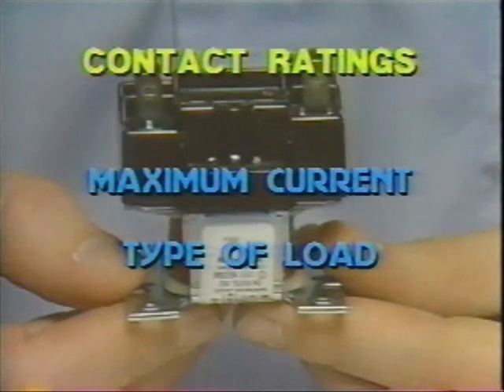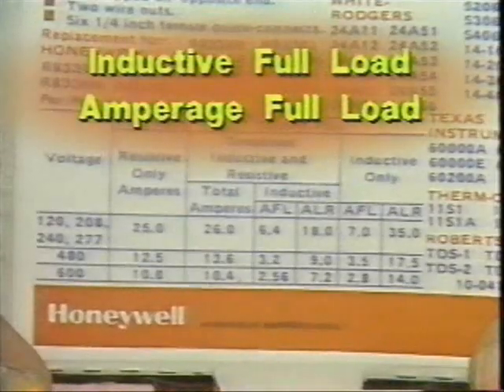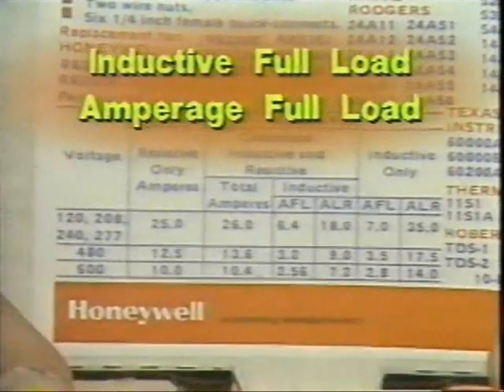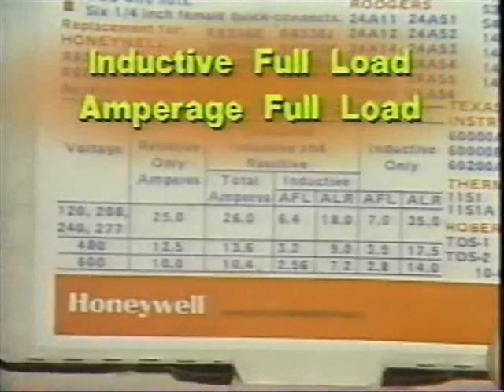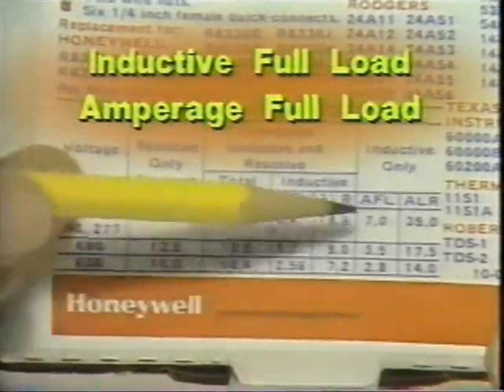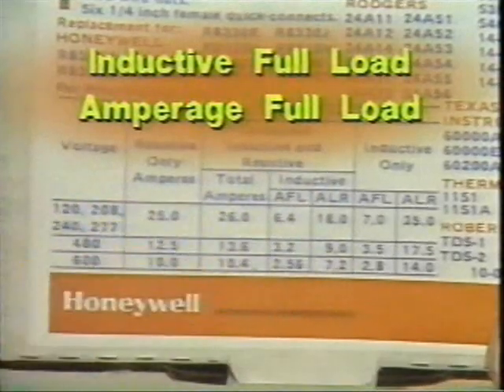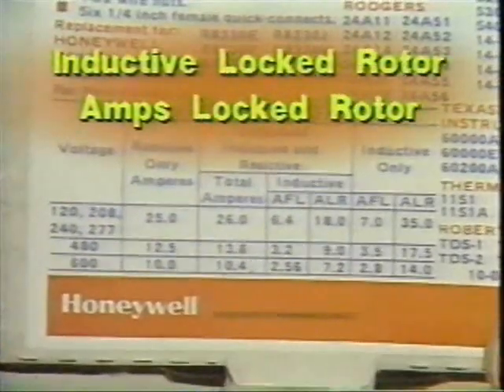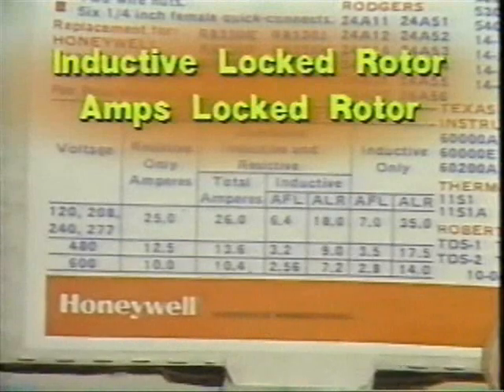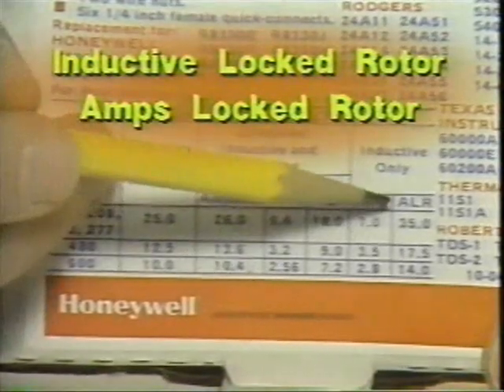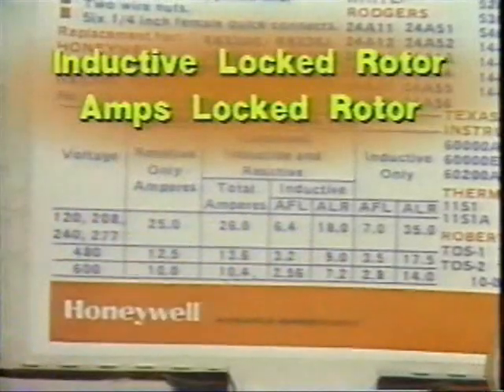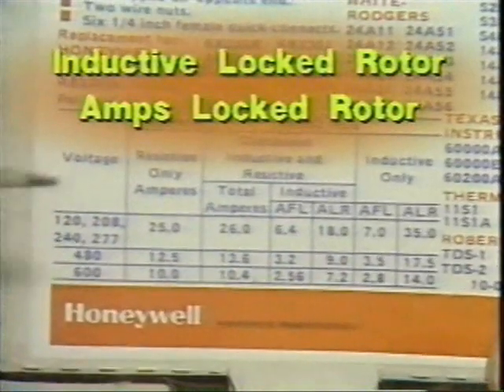Many relays are rated for several different voltages, and normally load ratings apply to each pole. Inductive full load, or sometimes amperage full load, is the number of amps a contact can handle on a continuing basis, such as a running motor. Inductive locked rotor, or amps locked rotor, relates to the instantaneous current flow a set of contacts sees when starting an inductive load such as a motor.